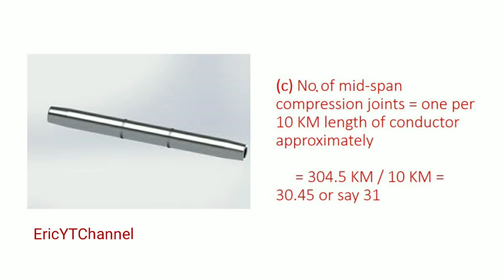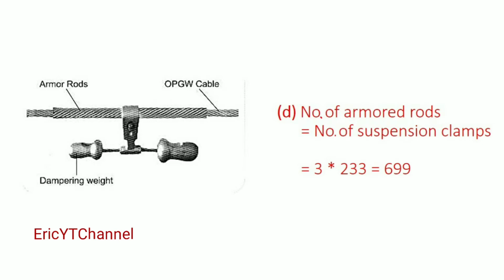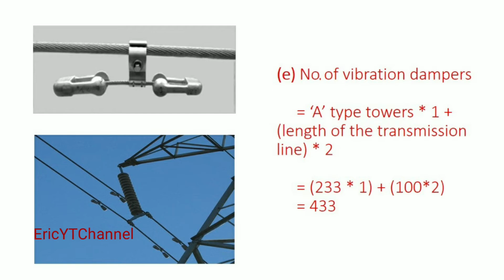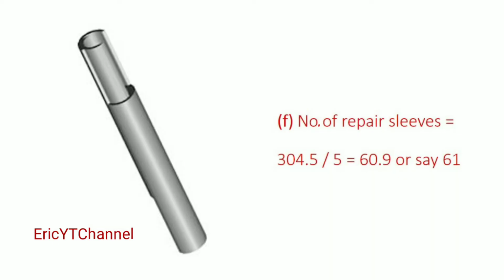Letter C, number of mid-span compression joints equals 1 per 10 km length of conductor, approximately 304.5 divided by 10 km equals 30.45, say 31. Letter D is number of armored rods equals number of suspension clamps equals 3 times 233 equals 699. Letter E is number of vibration dampers equals A-type towers times 1 plus length of the transmission line times 2 equals 233 times 1 plus 100 times 2 equals 433. Letter F is number of repair sleeves equals 304.5 divided by 5 equals 60.9, or say 61.